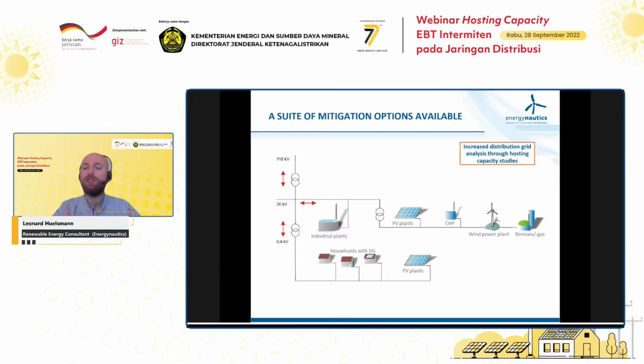And one measure is actually doing more of these hosting capacity studies, because if you analyze your network, you will know what your technical limits are, and then you can also allow PV applications and PV capacity in your network up to this limit. You can also do more distribution grid monitoring in order to see what is exactly happening in your distribution network. But always you need to bear in mind that monitoring devices will have more cost involved. So always you need to balance the mitigation measures with the cost associated to it.